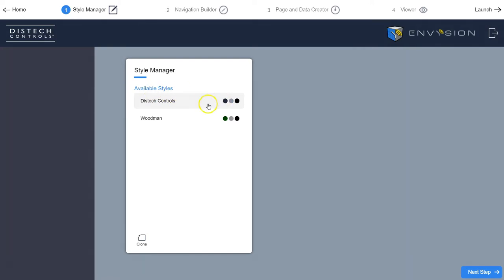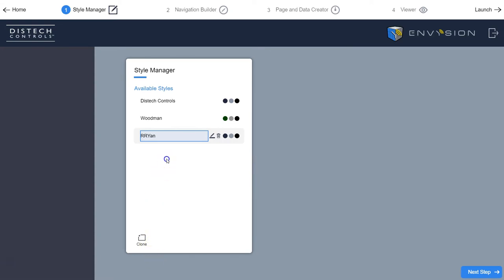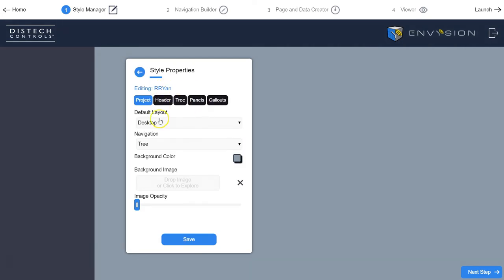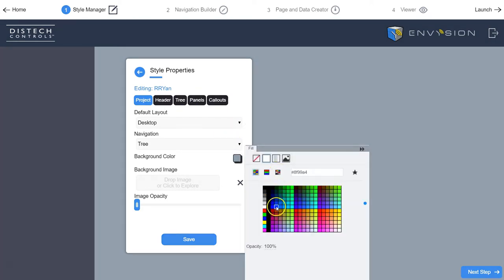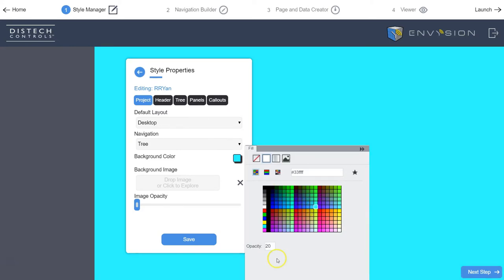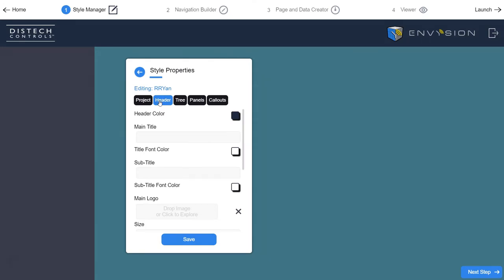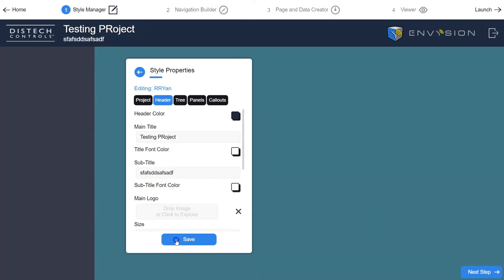To customize a style, clone an existing one — for example, clone 'Distech Controls,' name your new style, then hit the pen-to-paper button to edit it. That's where you adjust background colors, header colors, titles, and so on. I recommend pulling up an air handler or something you've already built while editing the style, so you can see how elements update as you change colors — otherwise you might accidentally make text invisible against the background.